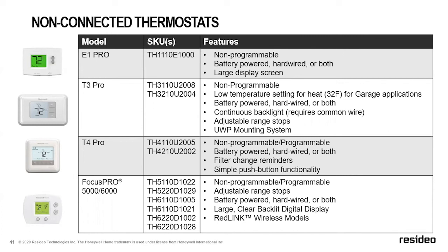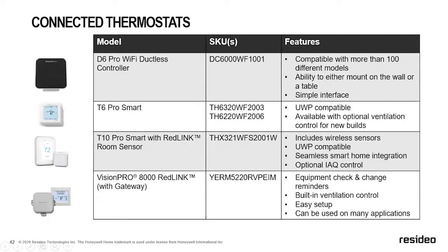Moving on, we also have the connected versions of thermostats I'd like to highlight. The top one there is a D6 Pro. So that D stands for ductless. If you're installing ductless units, we have a device that's compatible with more than 100 different models of heads. Whether you're working on different manufacturers' heads, you just program this device with 6 setup questions. 2 of those questions are what make and what series number, and it's talking infrared to that ductless head.